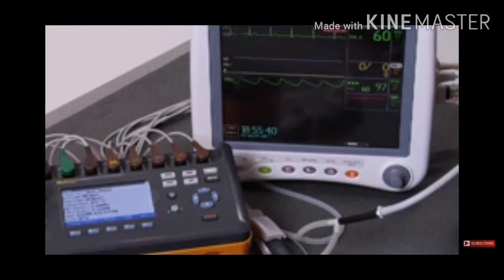And we are going to zero our invasive blood pressure transducers on the patient monitor at the very first step of what we do, followed by a selection of a simulation of all coordinated patient parameters. We'll do hypertensive first, followed by normal, followed by hypotensive, in order to assess whether we have a performing patient monitor.